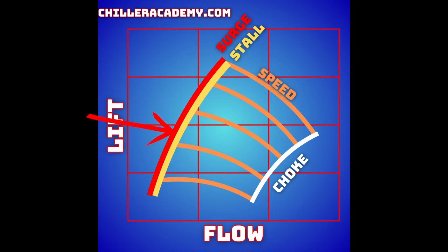So in this particular case, this is another way of representing that, right? So we have lift and then we have flow. So your pressure ratio is on this side, your RPM, say, down here. So if we're running at this RPM with this lift, where we line up right here on the graph, and our lift doesn't decrease, but we slow down, meaning we have less flow, then we move straight over to this point on the graph. And then we're beyond what our surge line is. So lower RPM pushes us into a surge, okay?